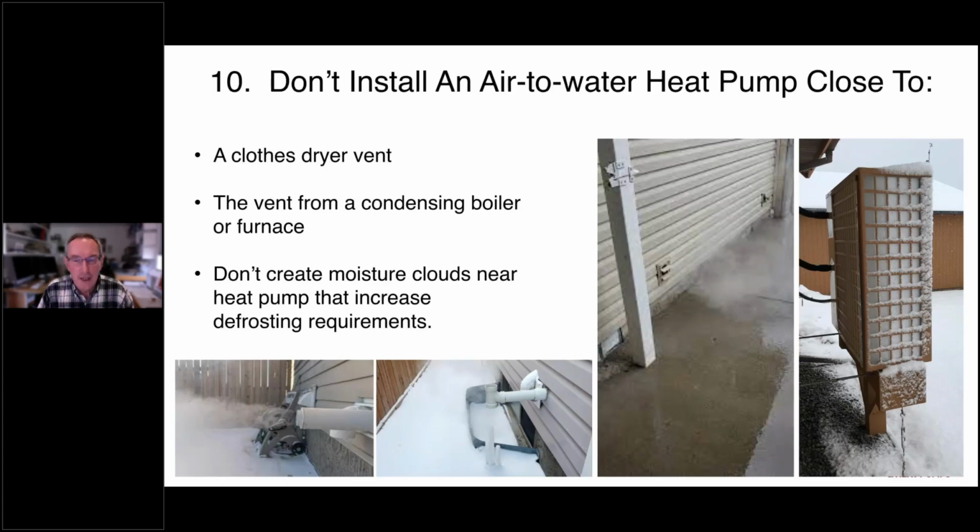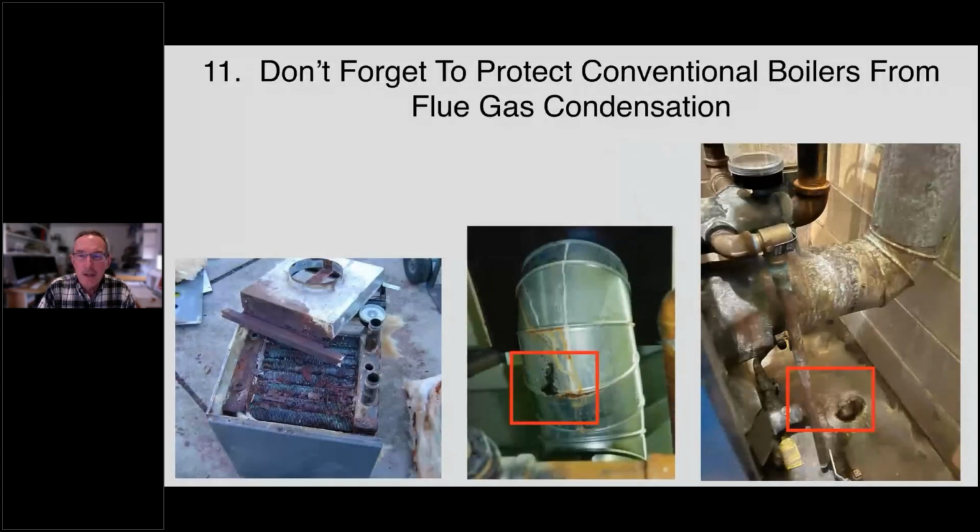You want to make sure that you get it away from potential plumes of moisture like this. Okay. Now, here's another one. I've seen this many, many times. When a conventional boiler is operated at conditions that cause sustained flue gas condensation.